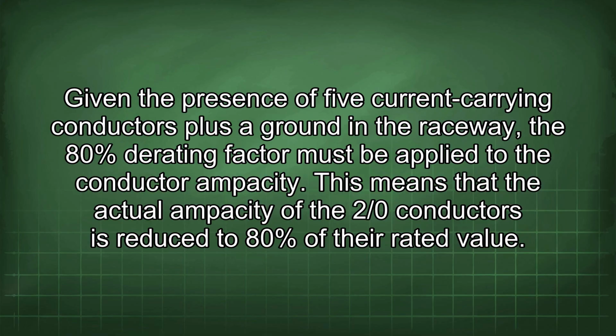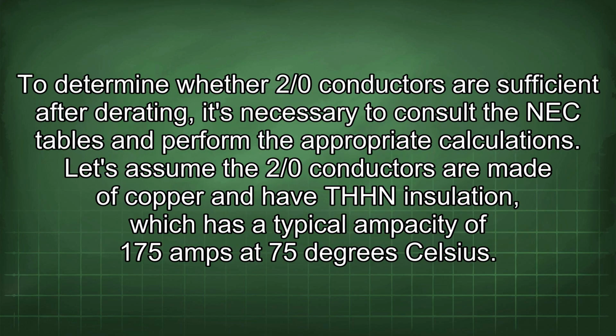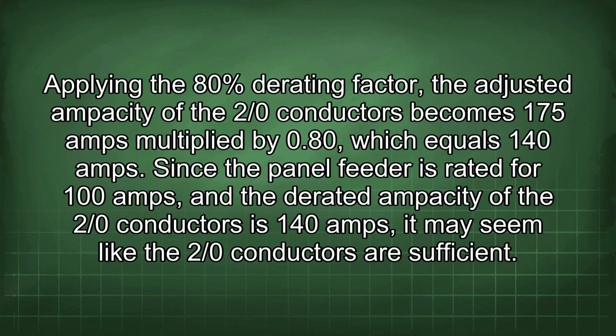This means that the actual ampacity of the 2/0 conductors is reduced to 80% of their rated value. To determine whether 2/0 conductors are sufficient after derating, it's necessary to consult the NEC tables and perform the appropriate calculations. Let's assume that 2/0 conductors are made of copper and have THHN insulation, which has a typical ampacity of 175 amps at 75 degrees Celsius. Applying the 80% derating factor, the adjusted ampacity of the 2/0 conductors becomes 175 amps multiplied by 0.80, which equals 140 amps. Since the panel feeder is rated for 100 amps and the derated ampacity of the 2/0 conductors is 140 amps, it may seem like the 2/0 conductors are sufficient.